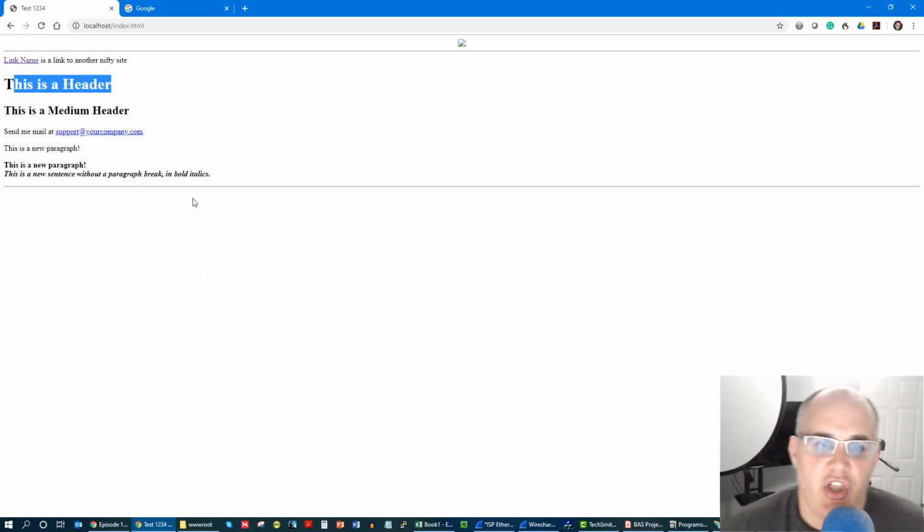Now, certain client-side functions will be validated at the web server or at the web page, which they should be. They should be validated on the client. Now, what do I mean by that? Well, if I have an input to change zone temp, right? I shouldn't be able to put in ABC as the zone temp value. That should be caught on the client side. So that's called client side validation. Now you have server side validation as well. And you want to have that definitely because that will ensure that you catch other things as well, making sure that if anything happens to slip through the web validation, you'll catch it on the server side.